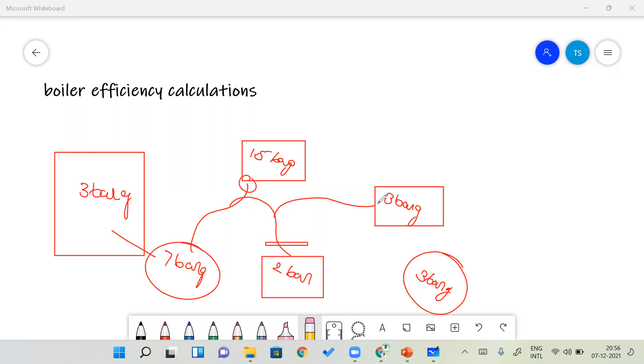And when it is required, I use a control valve. I can reduce it up to 1.5 bar, up to 2 bar, up to 3 bar. So these kinds of concepts will come in steam engineering. But you have to understand why the requirement is 3 bar gauge in a process industry, and why at the higher end of boiler production you are going up to 7 bar gauge. Why are you going with very high pressure? That is the major reason. The specific volume is a very, very important factor when you're talking about a boiler, and that is the major reason for the disasters.